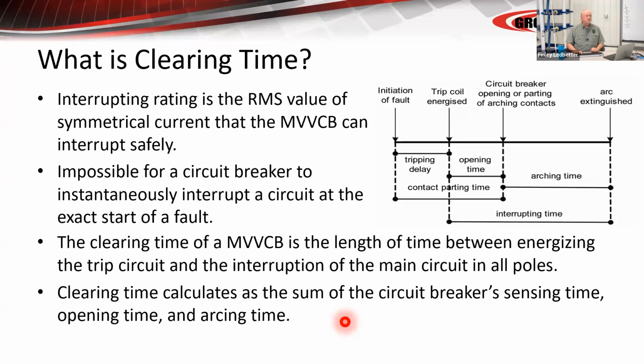I've got just about enough time to do this, and I wanted to get to it because it's very important. A lot of people don't understand what breaker timing is all about. When you actually send a signal for the breaker to trip, there's a certain amount of non-intentional time delay before the trip coil is energized. Then there's a little bit of time between the trip coil being energized and the contacts beginning to move. This part is inherent to the system. Then there's some mechanical delay due to lubrication and other factors.